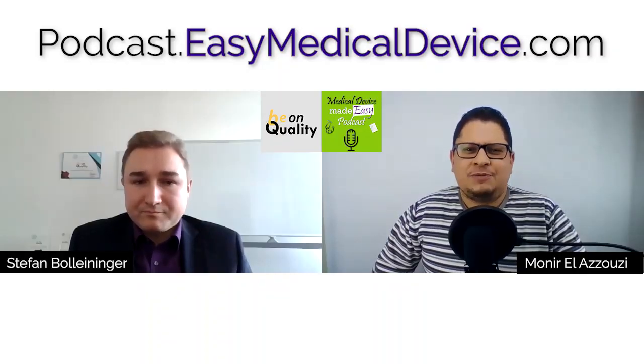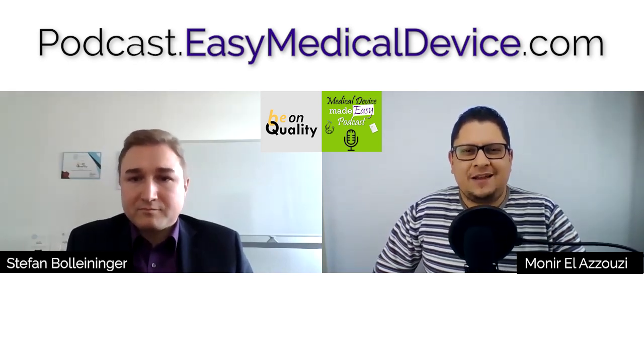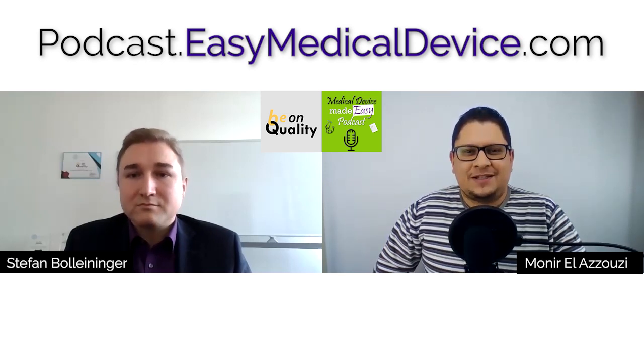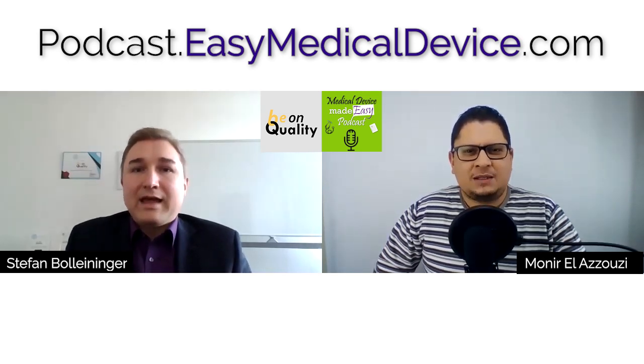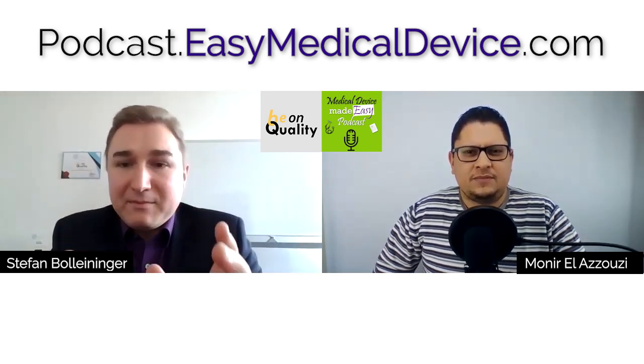So, Stefan, as we've said, we have the new medical device regulation that is asking for a quality management system. I think it's new. It's not something that was asked before with the MDD. Yes, most likely. Well, a quality management system was always a good idea, because it controls your organization and helps to streamline and perform. So that's a good thing. And the MDR says directly, you really need to have a quality management system, and depending on the classification, it needs to be either certified or not.